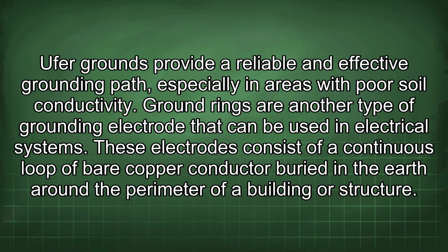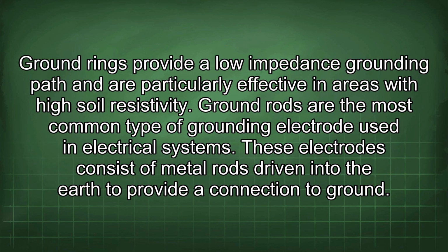Ground rings are another type of grounding electrode that can be used in electrical systems. These electrodes consist of a continuous loop of bare copper conductor buried in the earth around the perimeter of a building or structure. Ground rings provide a low impedance grounding path and are particularly effective in areas with high soil resistivity.